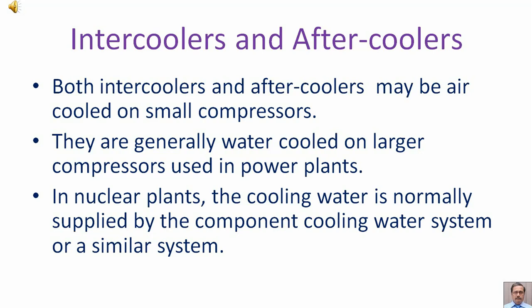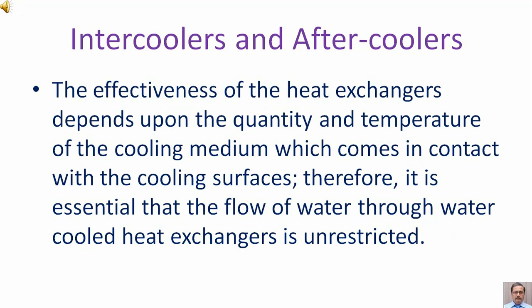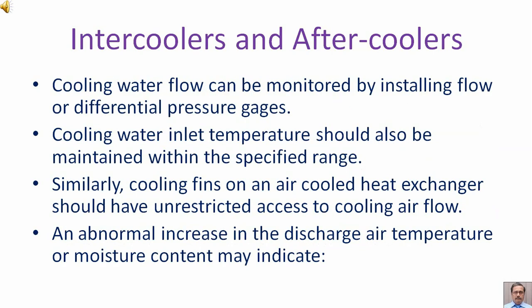Used in power plants and nuclear plants, the cooling water is normally supplied by the component cooling water system or a similar system. The effectiveness of the heat exchangers depends upon the quantity and temperature of the cooling medium which comes in contact with the cooling surfaces. Therefore it is essential that the flow of water through water cooled heat exchangers is unrestricted. Cooling water flow can be monitored by installing flow or differential pressure gauges.